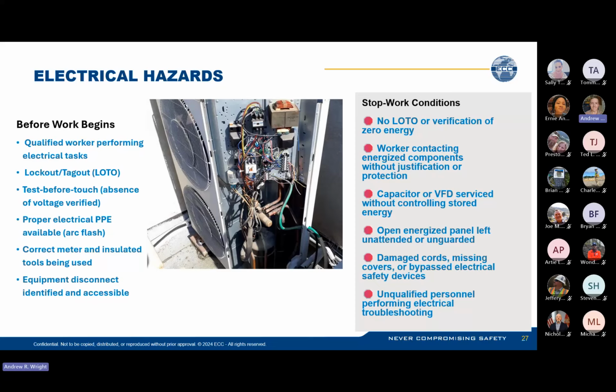So what are some stop work conditions that may come up if you're like an SSHO? You go up to a system and you see that they got the electrical panel open on an HVAC unit, and you go to where the main panel is, and you see that it has no lock on it, that it's on or maybe it's off, and they didn't put a lock on it. That's a stop work.